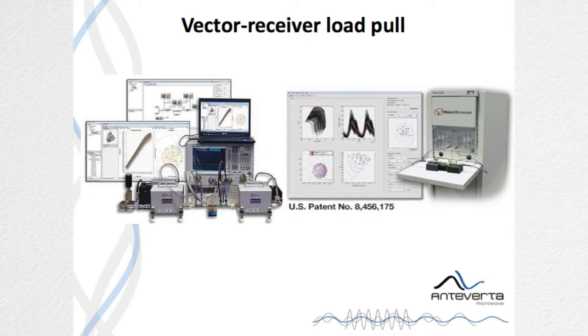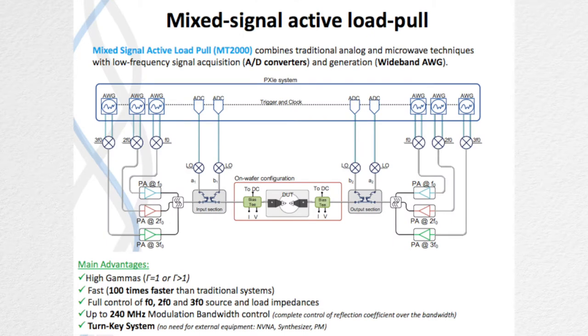These are a couple of examples. This is a system that's based on a conventional network analyzer with passive tuners. It can be a hybrid system, which means it can have active tuners as well as passive tuning. This example here is that of a mixed signal active load pull system. A mixed signal active load pull system is also a vector receiver load pull system. The main difference between a conventional vector receiver system and this system is that this is a completely turnkey solution. We have a dedicated VNA or NVNA, and we have dedicated signal sources.